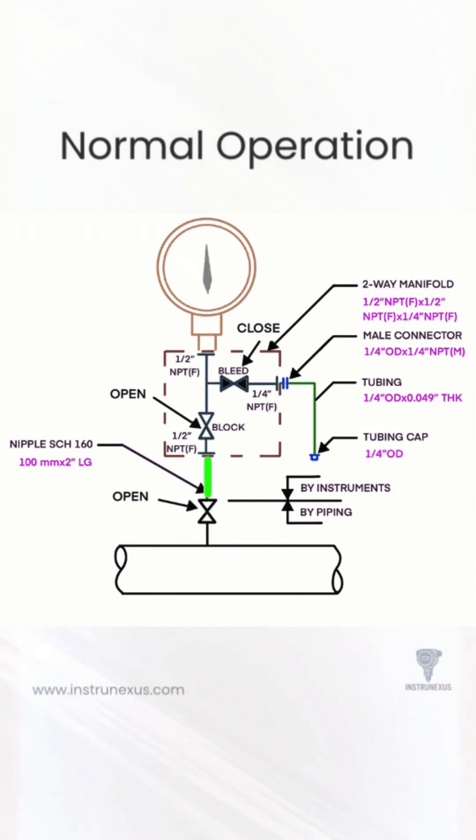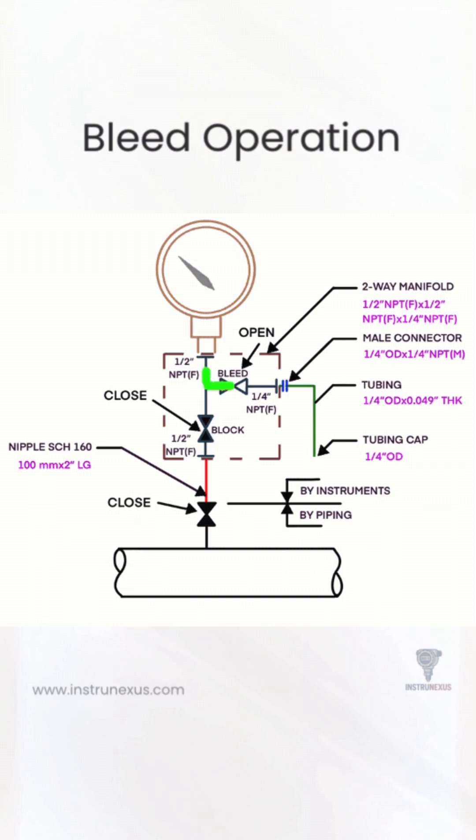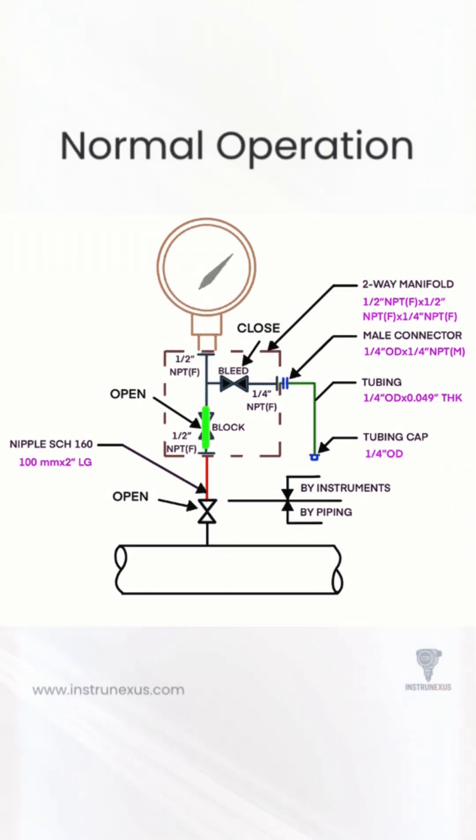Next, the two-way manifold includes a block valve and a bleed valve. The block valve isolates the pressure gauge from the process. The bleed valve releases trapped pressure before removing the gauge for calibration or replacement.